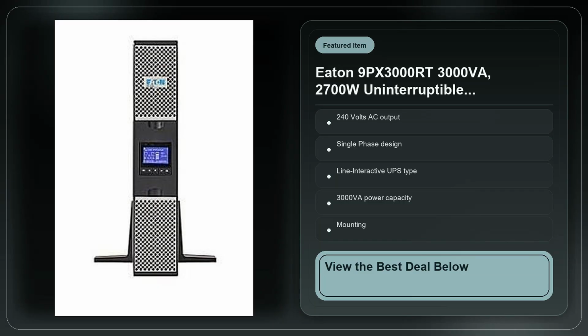The LCD, or the optional display panel depending on your configuration, showed the load hovering around 45%. That's well within its sweet spot, and it gave me roughly 12 minutes of battery time before I could safely shut everything down or wait for the grid to stabilize. In practice, that buffer is more than enough for most small businesses. You can finish a print job, close a database, or simply ride out the glitch without a panic.